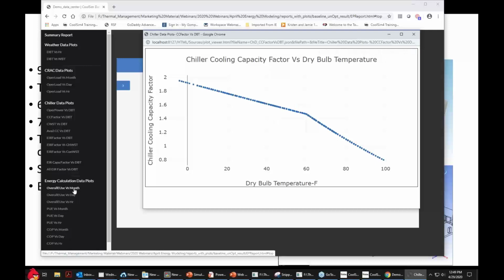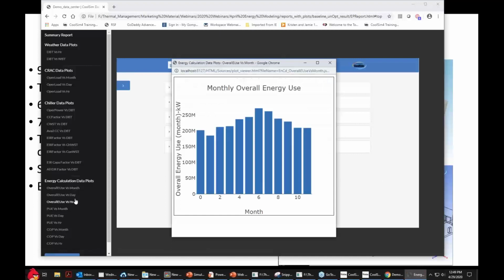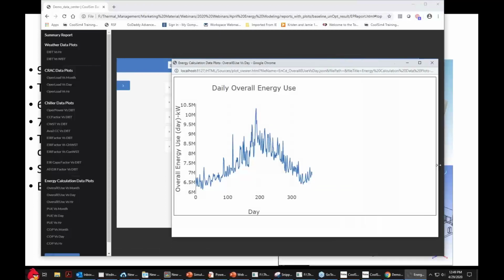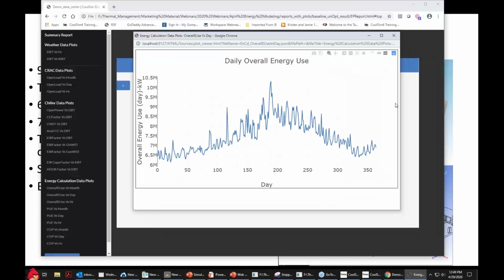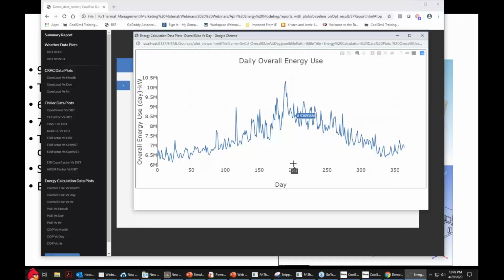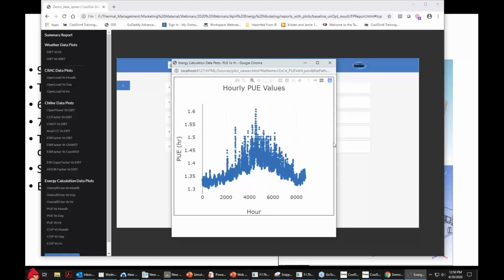Down here we have use per month. So this is monthly usage. I was going to look at daily energy usage as well, days in the year. It's actually interesting to look at PUE and how the difference in granularity affects the variation in PUE. So a monthly PUE is going to be almost constant, whereas an hourly PUE is going to have a lot more variation in it. So here's the hourly PUE.